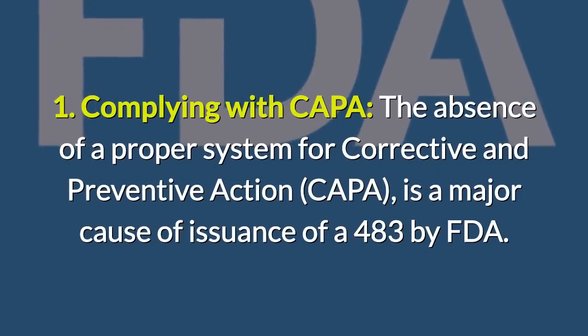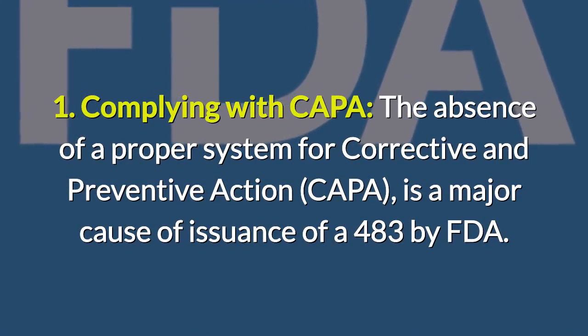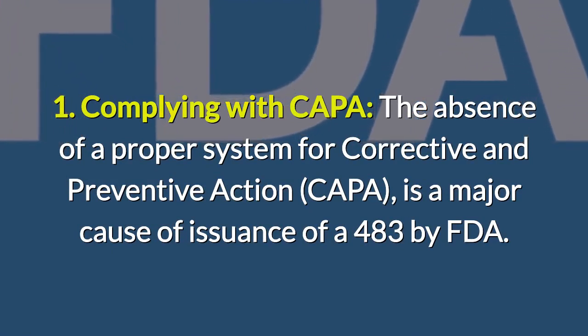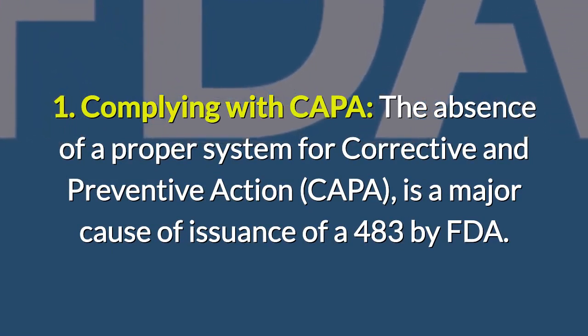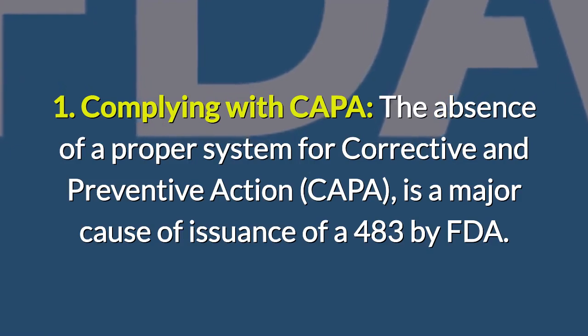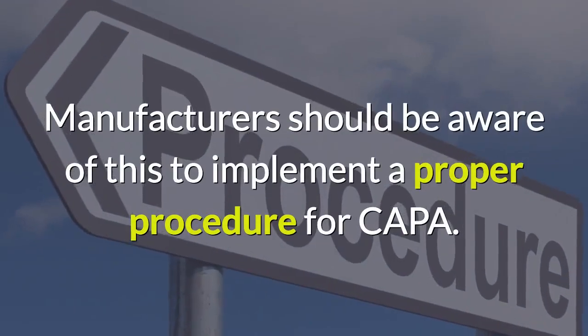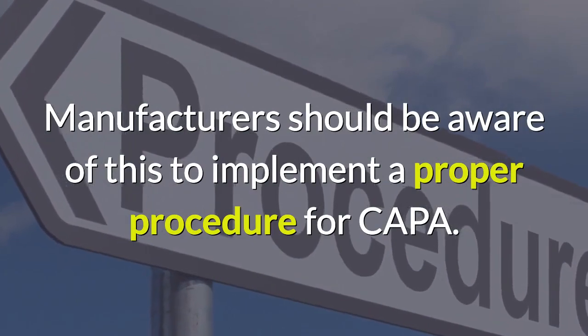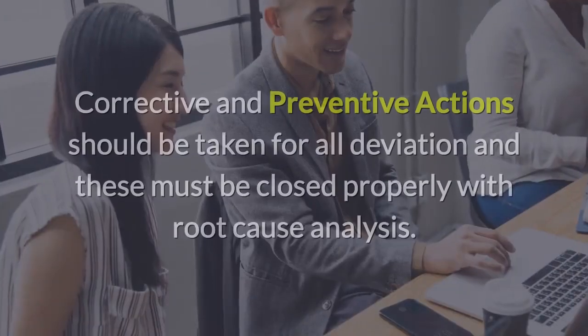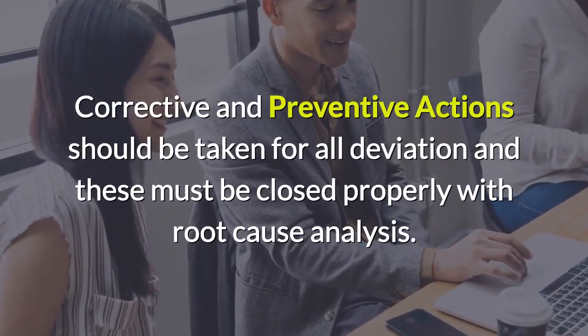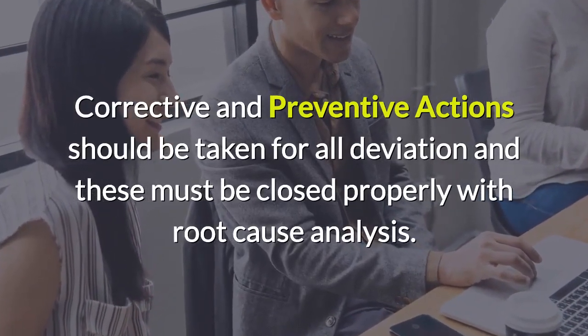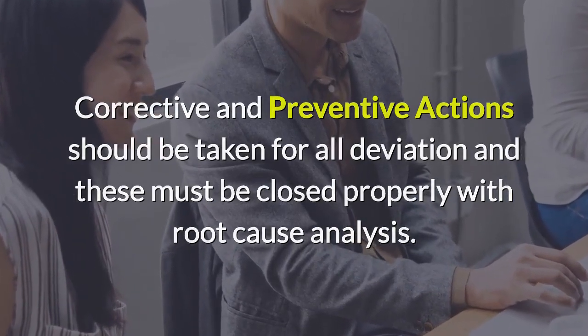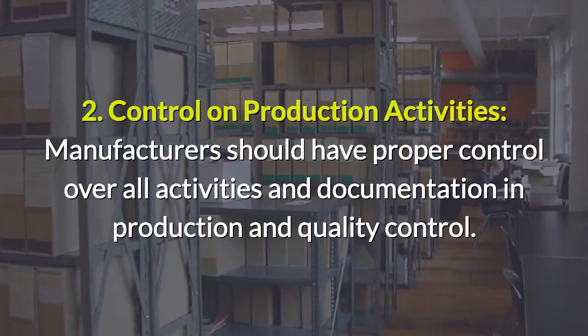1. Complying with CAPA. The absence of a proper system for corrective and preventive action (CAPA) is a major cause of issuance of a 483 by FDA. Manufacturers should be aware of this and implement a proper procedure for CAPA. Corrective and preventive actions should be taken for all deviations, and these must be closed properly with root cause analysis.